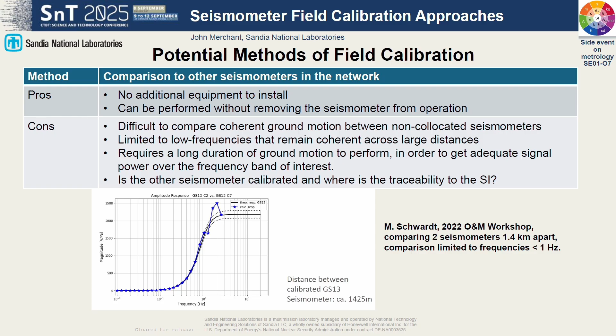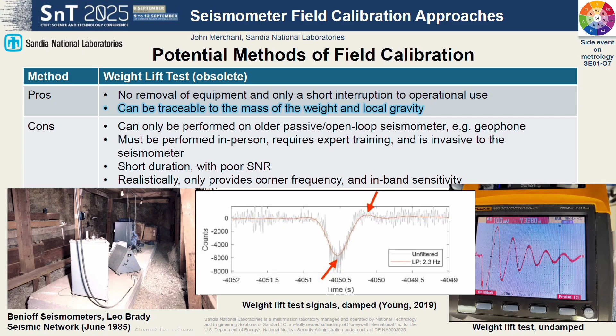Horst talked about this technique of performing a weight lift test. You expose the seismometer, you put a mass on top of its proof mass, pull it off, and you can look at things. You see these two plots of either the damped or undamped output of a seismometer when you've conducted a weight lift test. And yes, you can tell things about the free period, the damping, the in-band sensitivity, but it's very difficult, and these are hard measurements to make over very short durations. The other is that it's invasive. Horst mentioned that it takes an expert analyst on site, cracking open these seismometers to do this, and also it's not really suitable for current active feedback broadband seismometers anymore.